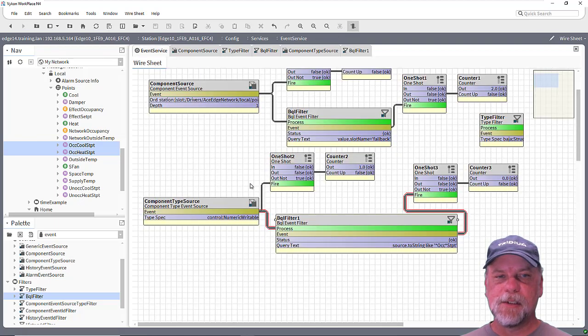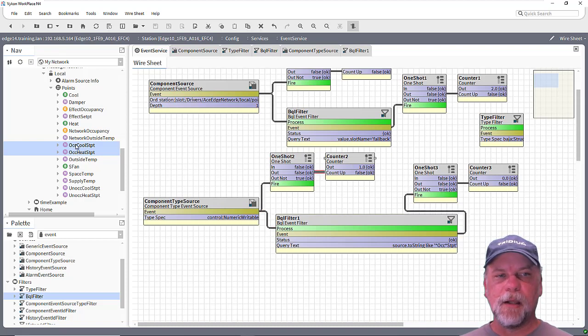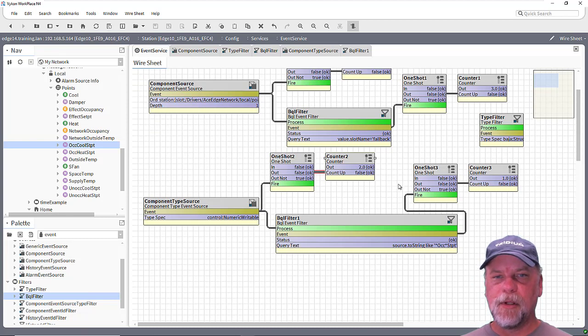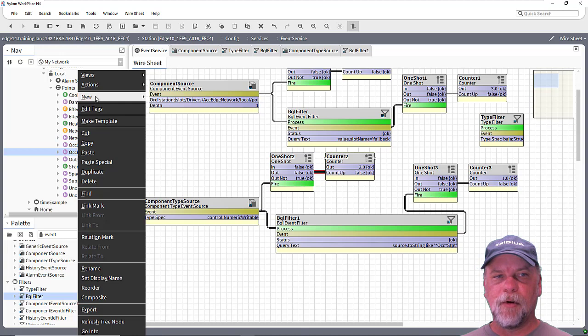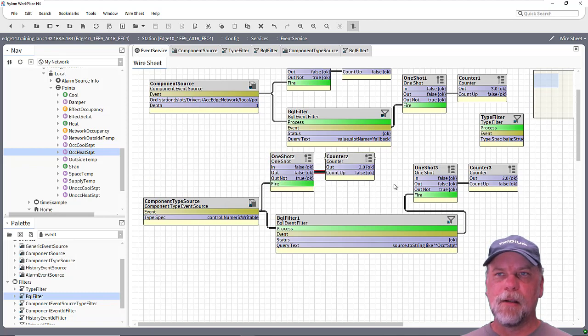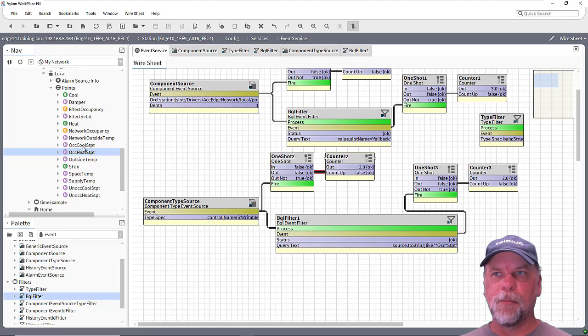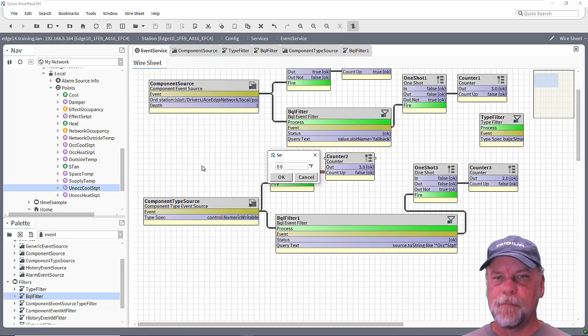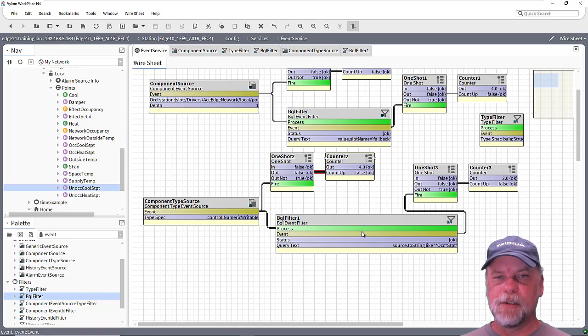So if I look at the event service here again, there's just the one event here that initially I did. So if I set the fallback on the OCC cool set point, you can see it fired an event on both of the counters. And if I invoke maybe an override action on OCC heat set point for one minute, then we'll see it fired again — the actions on both counters as well. So it's processing both the OCC heat and the OCC cool set point for any property changes. Now if I invoke a set or override action on the UNOCC cool set point, we'll see that the counter here incremented to four, but this counter on the filter did not. So the filter is effectively blocking out the UNOCC cool and UNOCC heat set point writables.